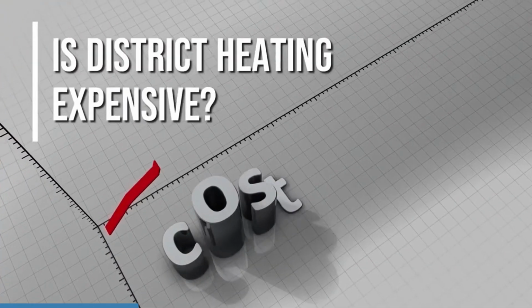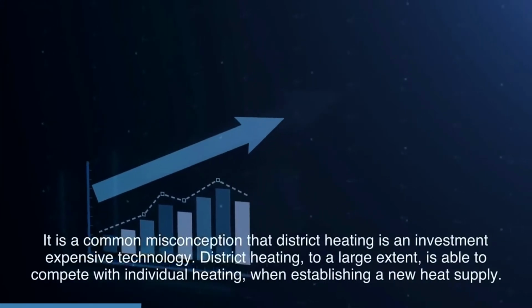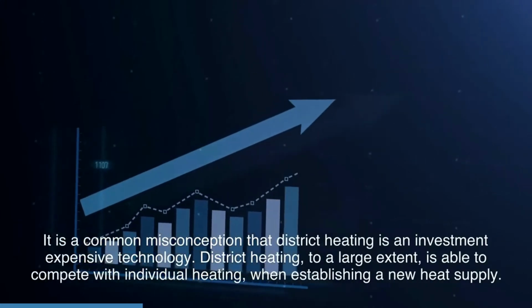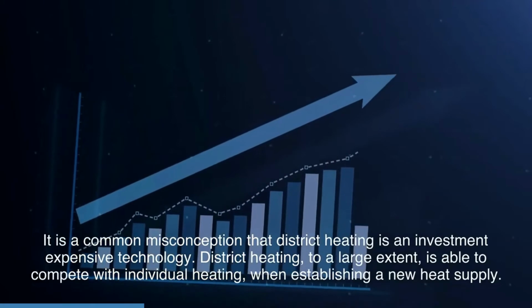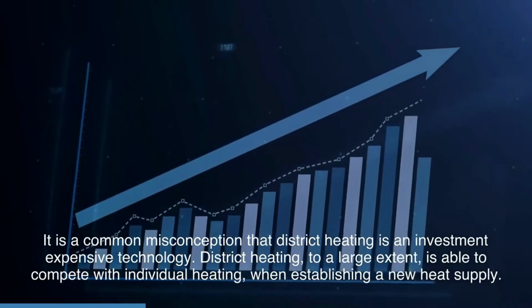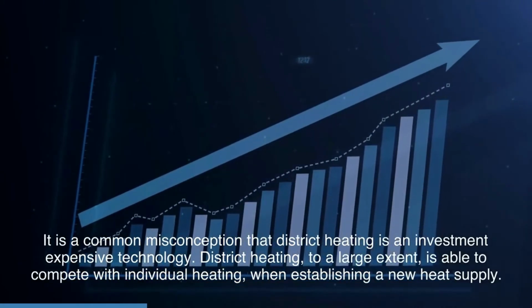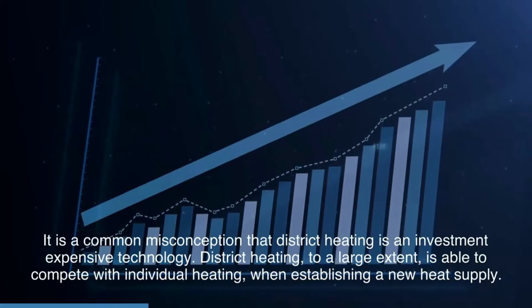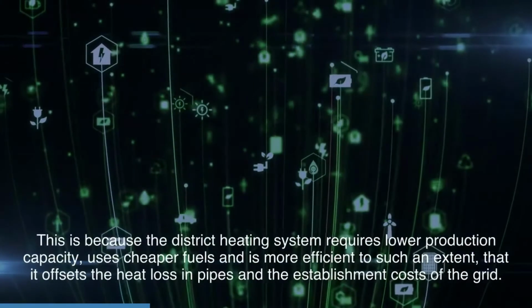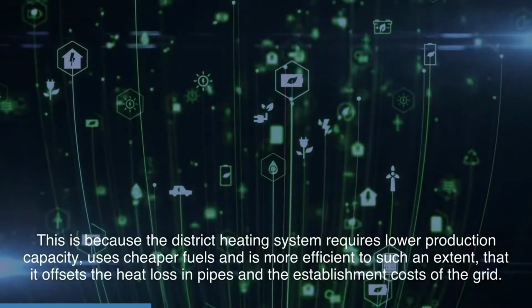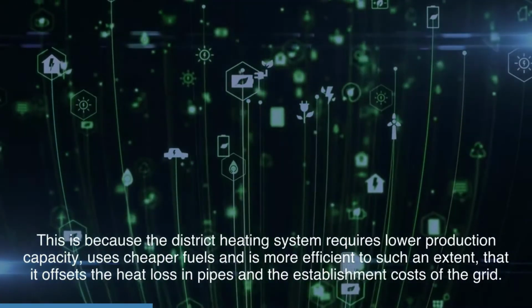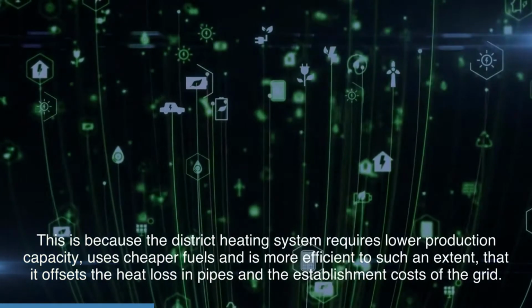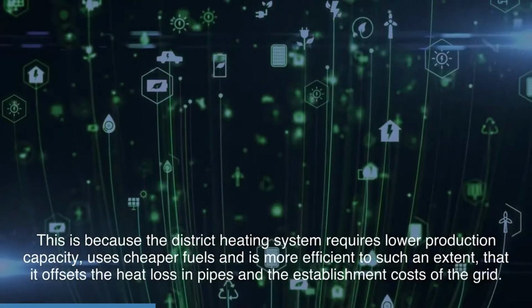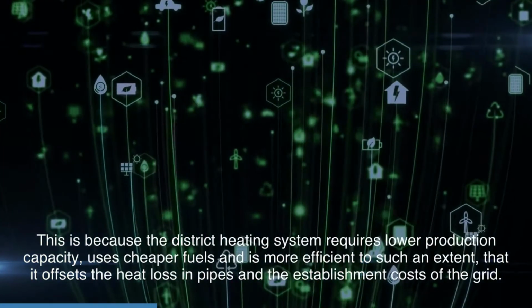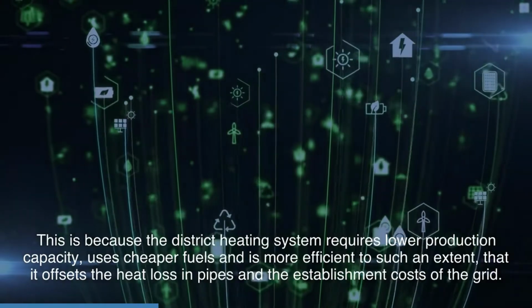Is district heating expensive? It is a common misconception that district heating is an investment-expensive technology. District heating, to a large extent, is able to compete with individual heating when establishing a new heat supply. This is because the district heating system requires lower production capacity, uses cheaper fuels, and is more efficient to such an extent that it offsets the heat loss in pipes and the establishment costs of the grid.